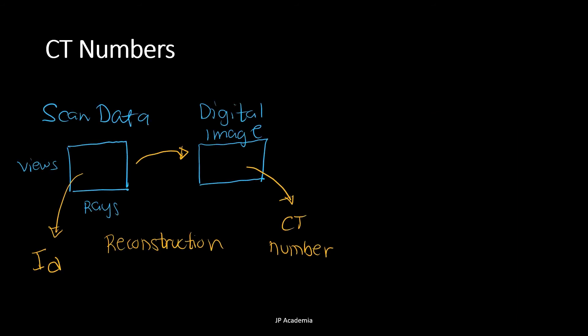Part of the CT reconstruction is a mathematical algorithm that converts the scanned data, we have the view and the rays here, into a numerical or digital image. This will generate an array of pixels, and each pixel has a numerical value called the CT number. Each value is specific to the density of tissue in the corresponding pixel or voxel. This generated digital image is then stored in the computer system of our CT machine.